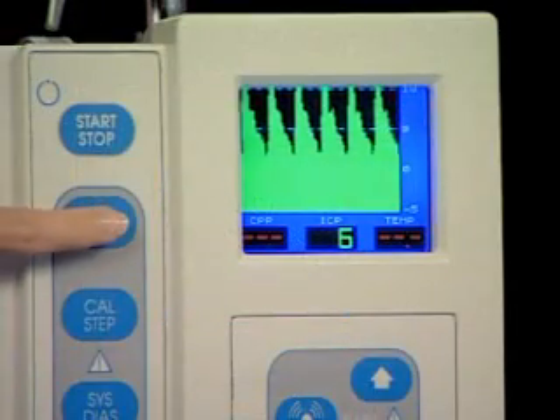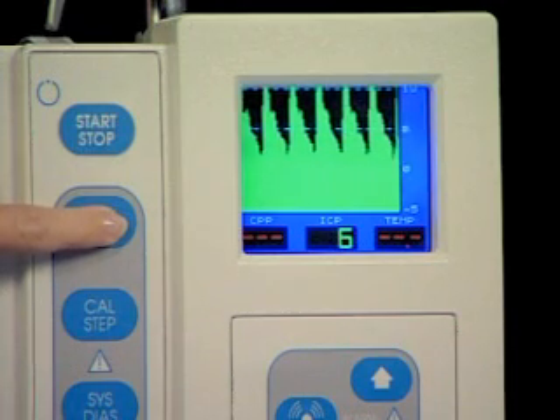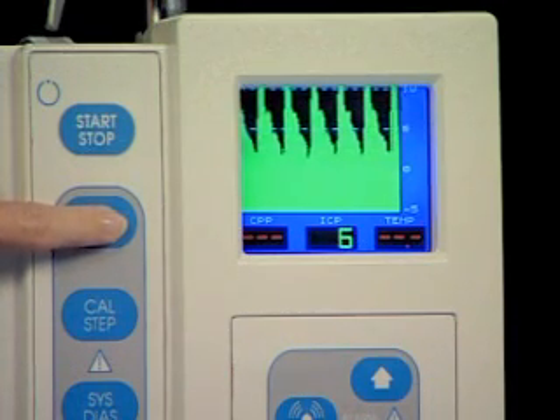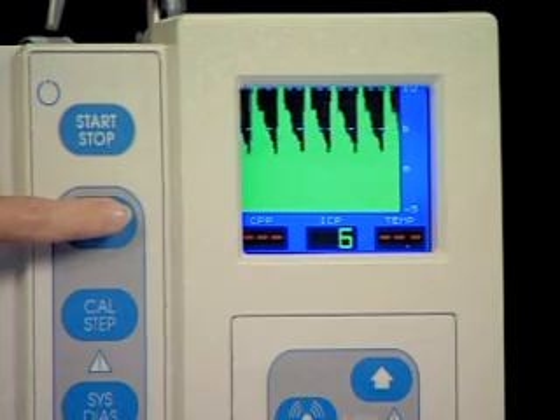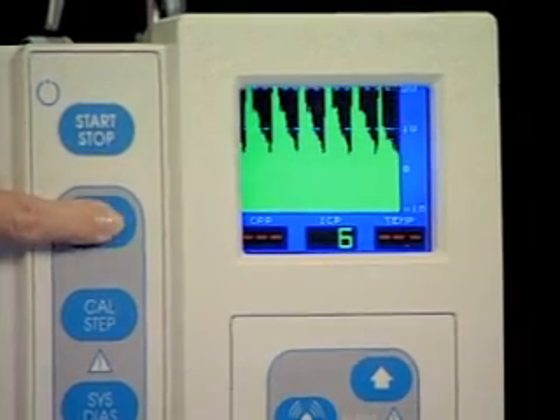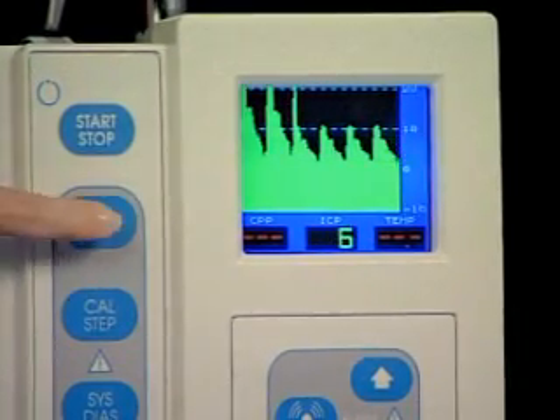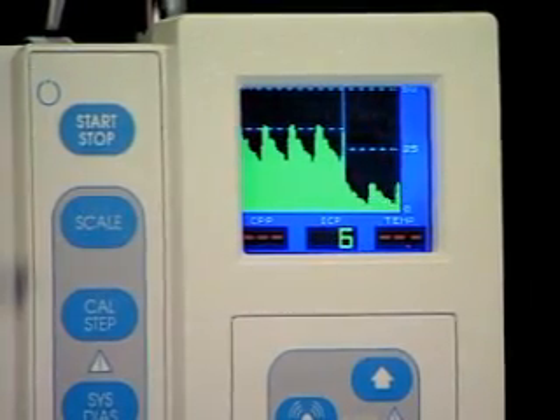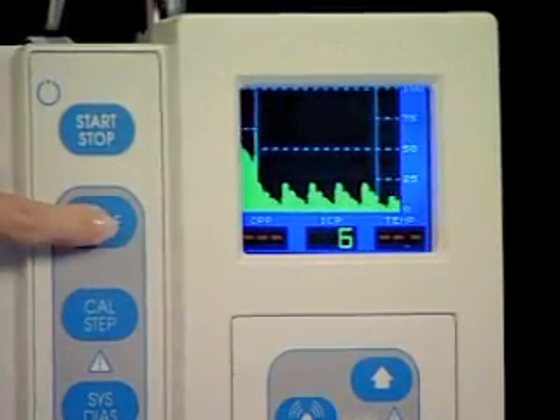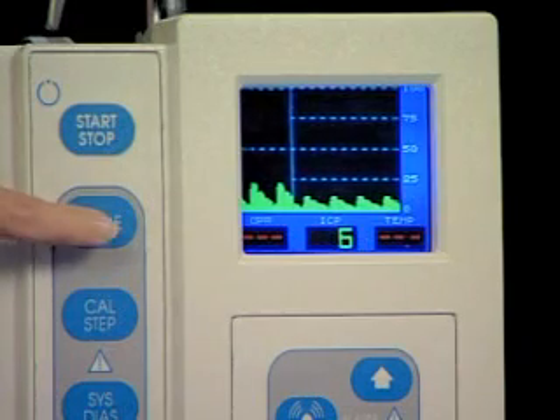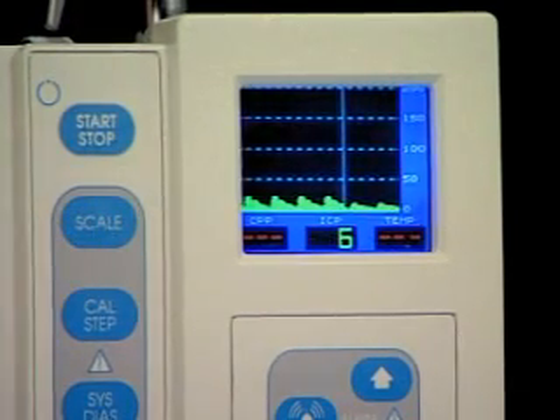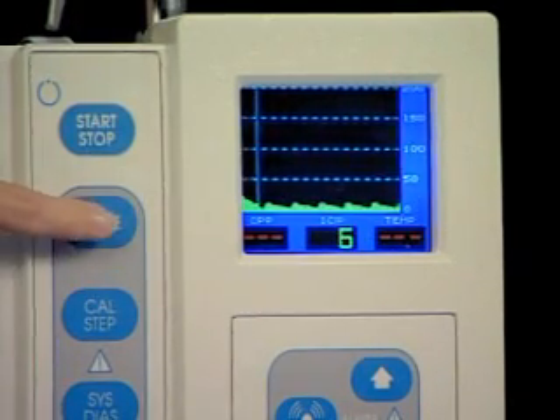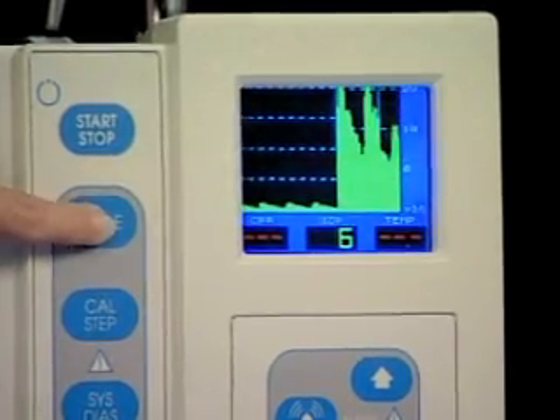The scale button is used to change the scale on the display screen. The scale ranges are -5 to +10 millimeters of mercury, -10 to +20, 0 to +50, 0 to +100, and 0 to +200 millimeters of mercury. The usual range setting is -10 to +20 millimeters of mercury.